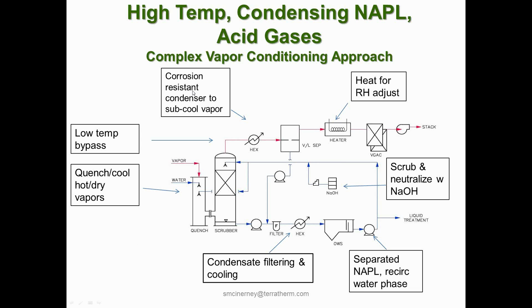So because we had the corrosion issues that I talked about earlier, this particular heat exchanger setup was a graphite unit, and we had much higher temperatures than 350 degrees Fahrenheit. So we really did need an initial cooling step, where we used a quench/scrubber system to knock down the temperatures from the high temperature dry vapors coming from the well field. Again, adding water, getting the evaporative cooling through that step, and then the resulting vapors exiting the scrubber would be at or slightly above 200 degrees Fahrenheit or so.